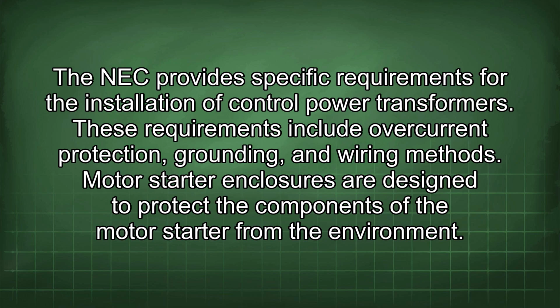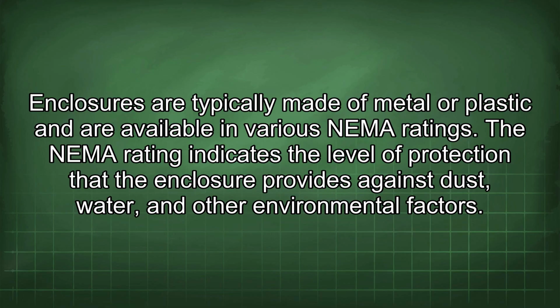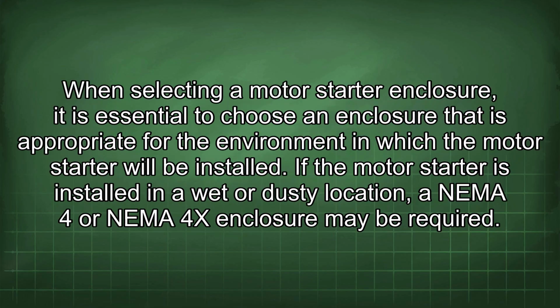Motor starter enclosures are designed to protect the components of the motor starter from the environment. Enclosures are typically made of metal or plastic and are available in various NEMA ratings. The NEMA rating indicates the level of protection that the enclosure provides against dust, water, and other environmental factors. When selecting a motor starter enclosure, it is essential to choose an enclosure that is appropriate for the environment in which the motor starter will be installed. If the motor starter is installed in a wet or dusty location, a NEMA 4 or NEMA 4X enclosure may be required.